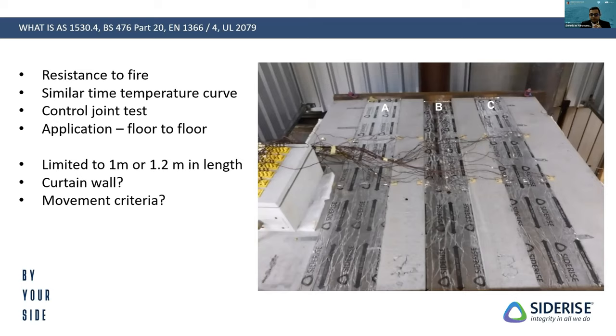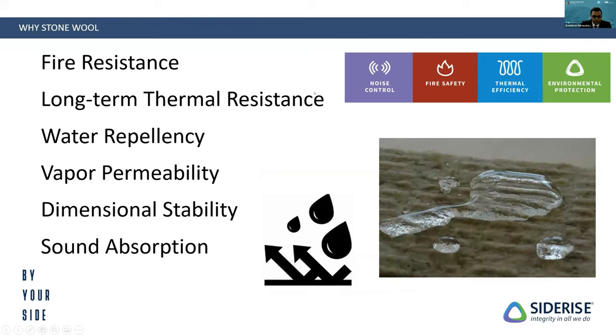There are further tests required to test the actual arrangement, because there are limitations in relation to the length of the specimen tested, and movement capabilities of the product are not always evaluated. When we talk about this void, the important material is stonewool. The reason we use stonewool is it has very good resistance to fire, good thermal value, can resist thermal insulation for longer periods, repels water, gives dimensional stability, can accommodate some movement when installed correctly, and is also good in relation to sound absorption.